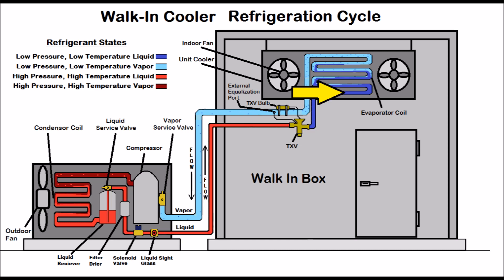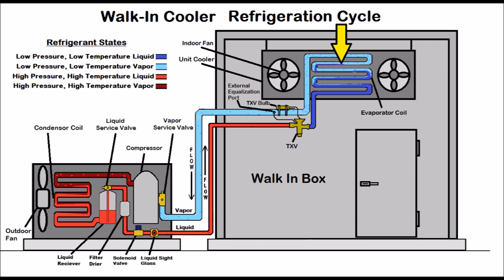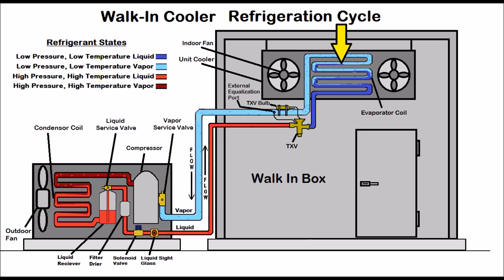As it heads into the evaporator coil it absorbs heat from inside the walk-in box. As it absorbs heat, the liquid refrigerant increases in temperature and turns into the saturated state where liquid and vapor both exist. That's where most of the heat is being absorbed. Once the refrigerant absorbs enough heat while maintaining the same temperature, it turns into a complete vapor, then continues increasing in temperature as it exits the evaporator coil. That temperature difference between where it becomes a complete vapor and where it exits the evaporator coil is called superheat — which is why the TXV bulb and external equalization port are mounted on the suction line right after the evaporator coil.